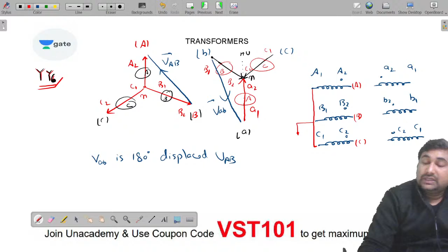After performing the polarity test on each transformer, we can mark the dots, represented by suffix 2. Similarly for transformer B, you can say B2, B1, and for C, small c2, c1. If you observe the connection, you will know what connections are possible. Here A1, B1, C1 can be shorted by an external wire, giving terminals A, B, C. If you observe, A2, B2, C2 are shorted to get 180 degree phase displacement, so shorting A2, B2, C2 gives you A, B, and C.